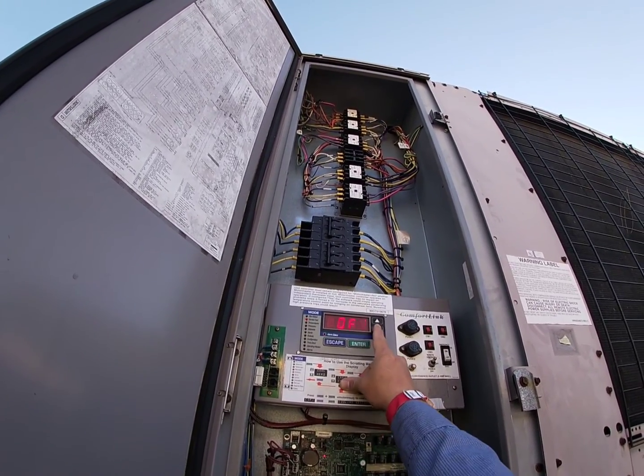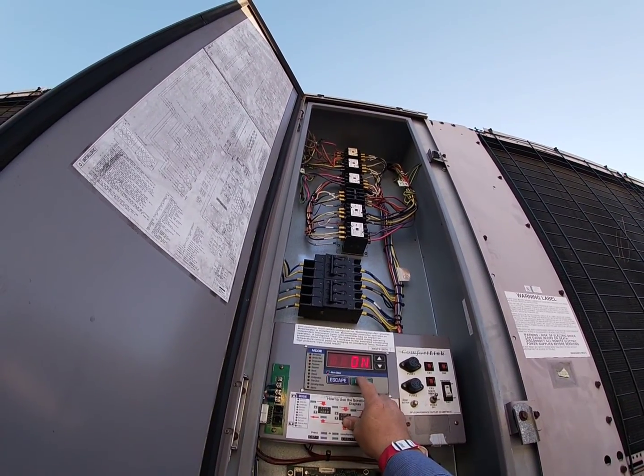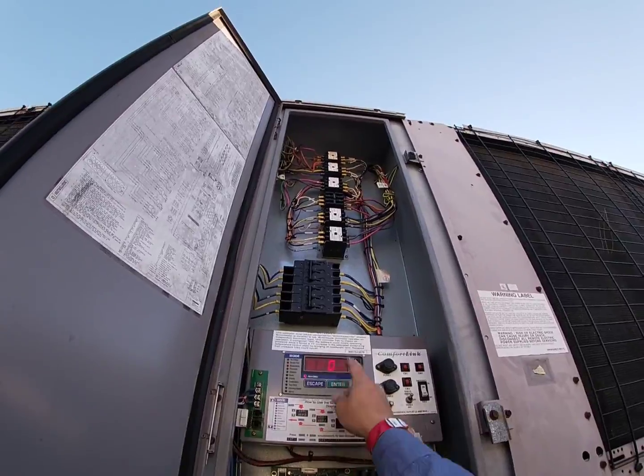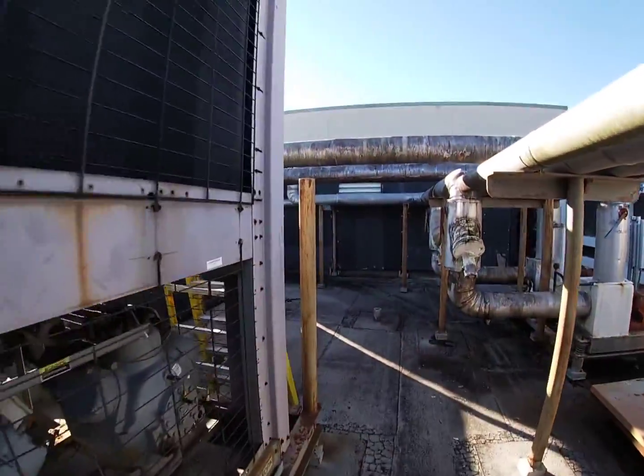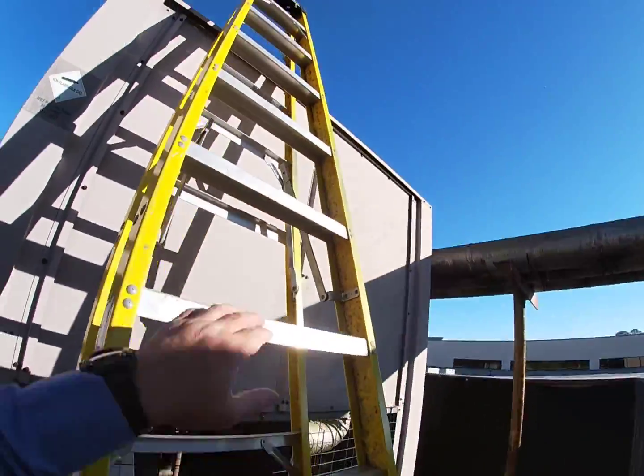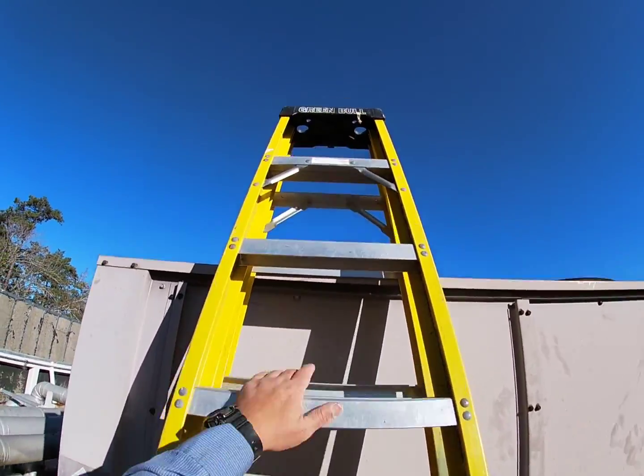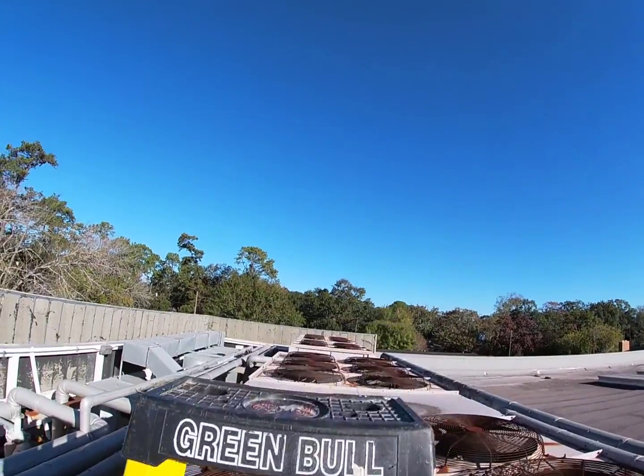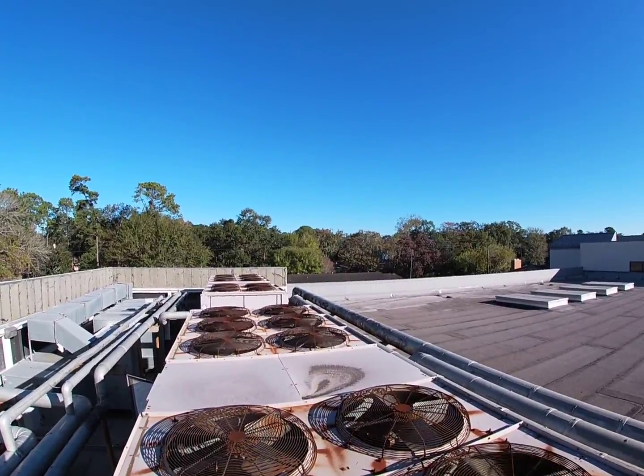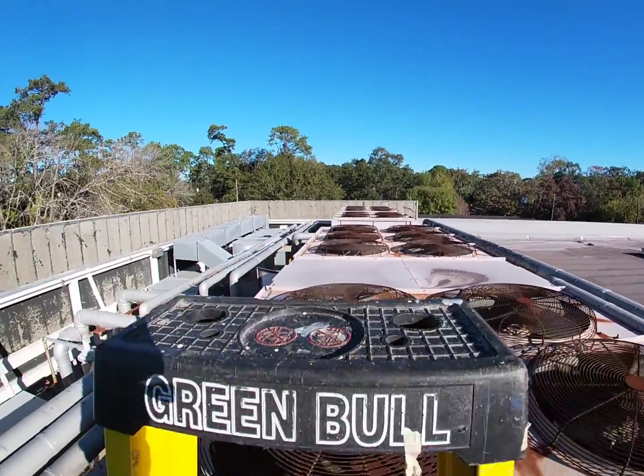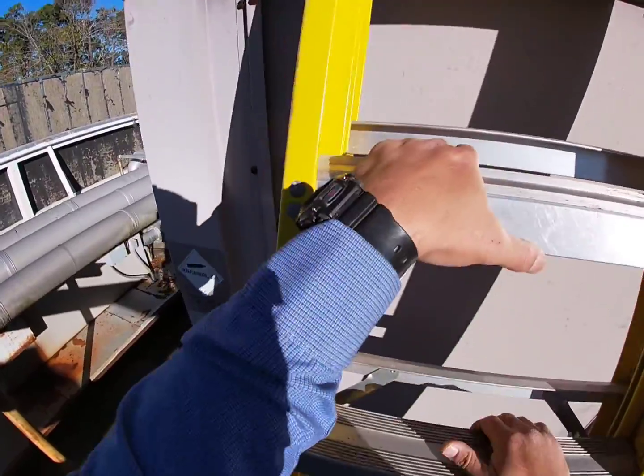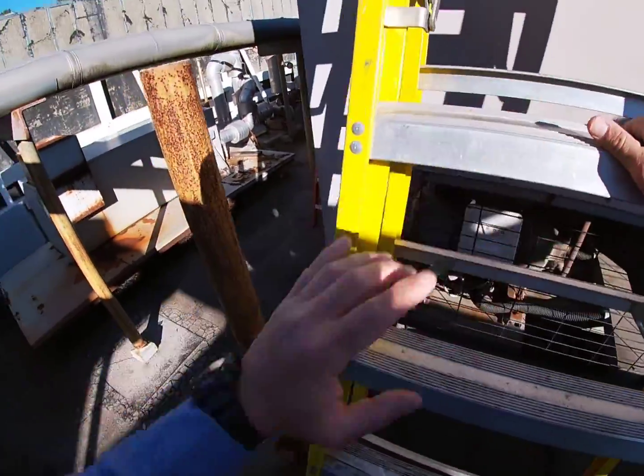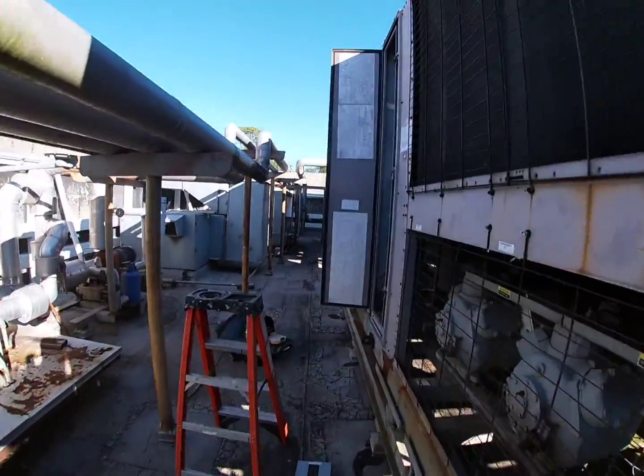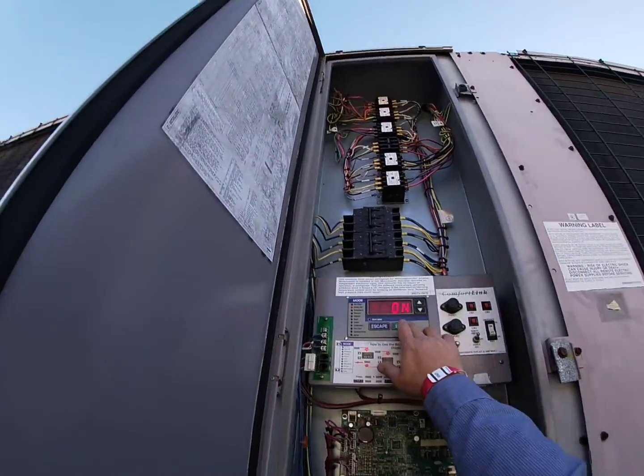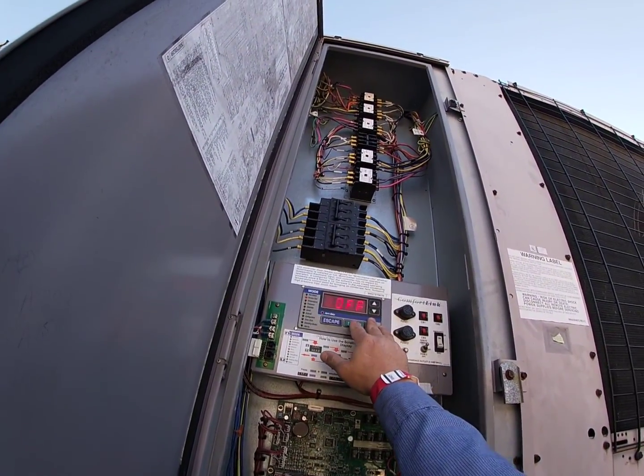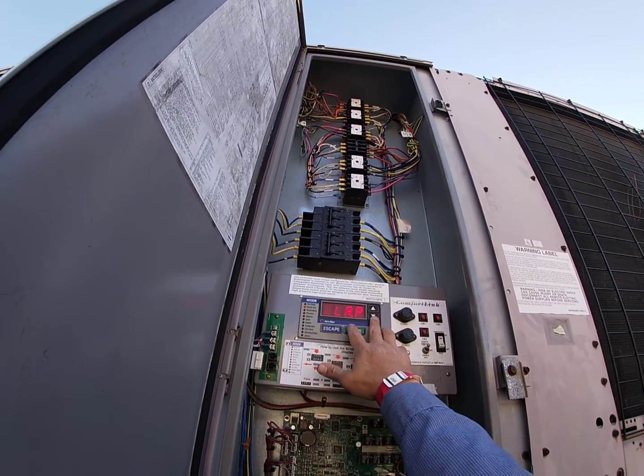Now we'll go to 4. So that's that other bottom contactor there. It's got two motors on it. Only hear one running, possibly two, so that's kind of hard to hear, but yeah, we have two. We got that center one over there and this one over here. We're okay there with that motor. So anyhow, we caught the culprit - it's just gonna be that one condenser fan motor there.